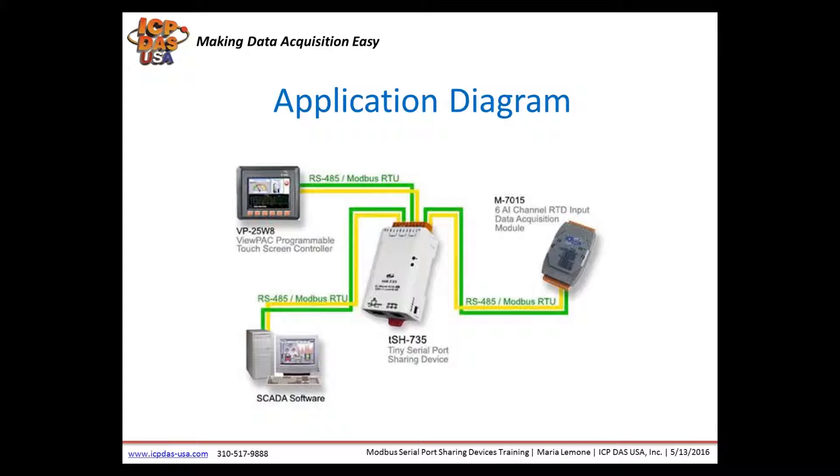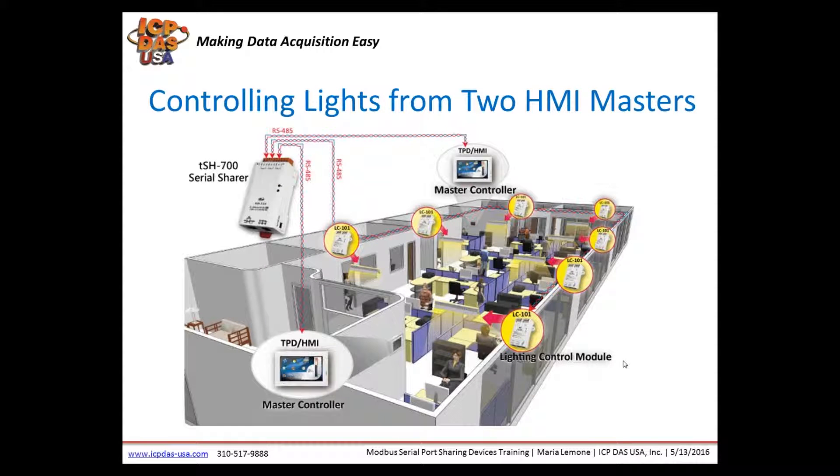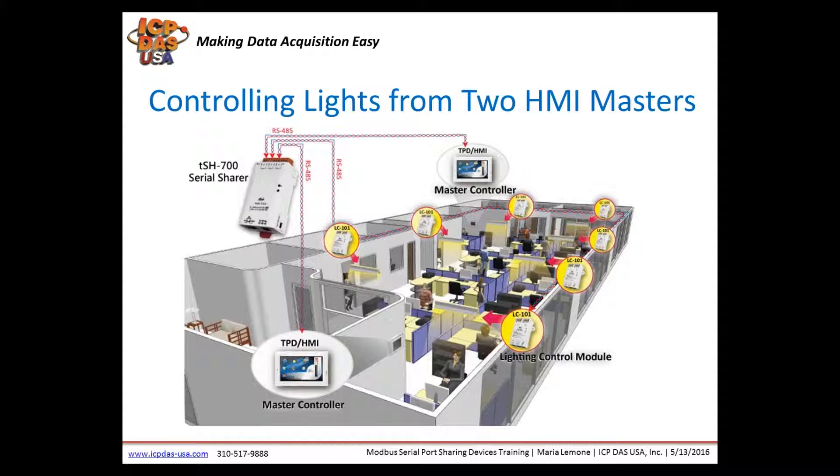The built-in read cache function is used to store requests and responses of Modbus messages in the TSH700 series memory buffer. When the other master controllers require the same information communication from the same slave RTU device, the cached response is what is returned immediately. The read cache function dramatically reduces the load on the slave serial port communication ensuring faster responses to the master, improving the stability of the entire system.